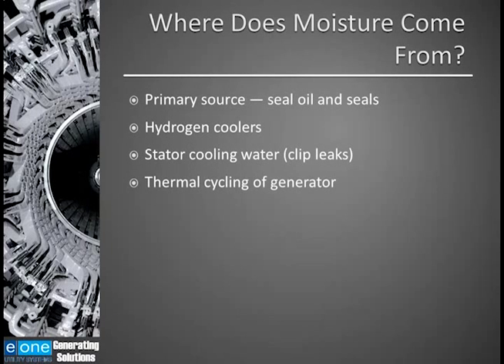Where does moisture come from? There are some installations where turbine lube oil and hydrogen seal oil are from the same source. They share the oil source. In this situation, steam from the turbine will force moisture into the oil. And if that oil is not properly treated and the vacuum pumps aren't operating properly, that moisture in the oil will be absorbed by the hydrogen in the generator. The hydrogen will actually act as a sponge and pull the moisture from the oil.